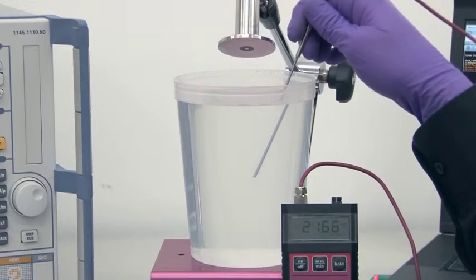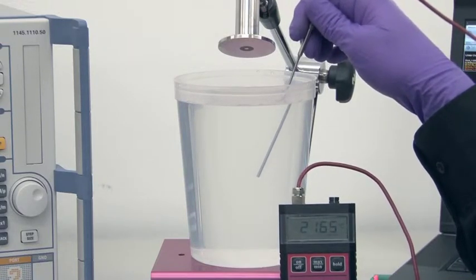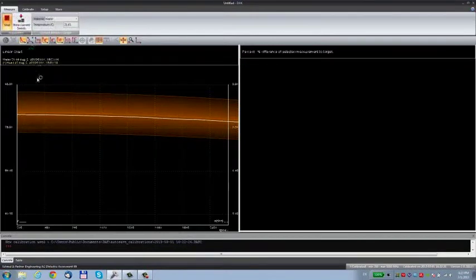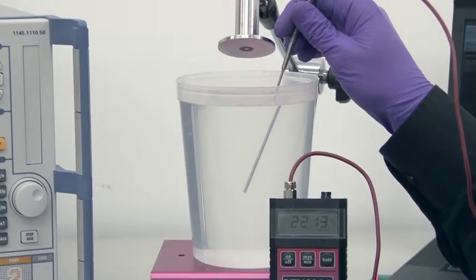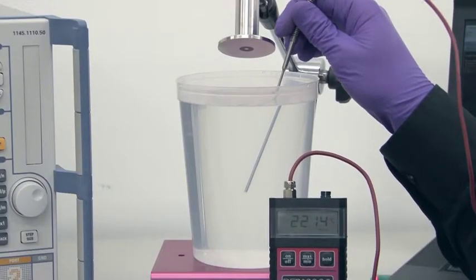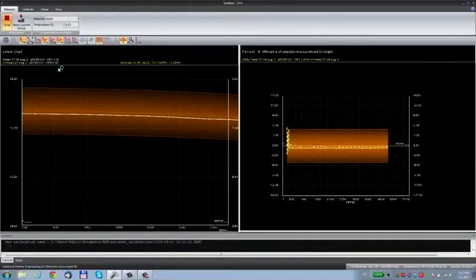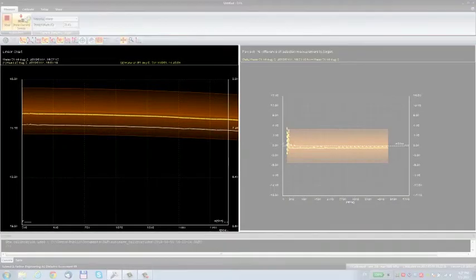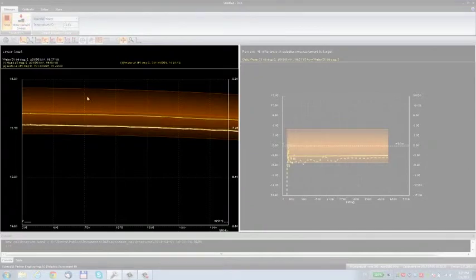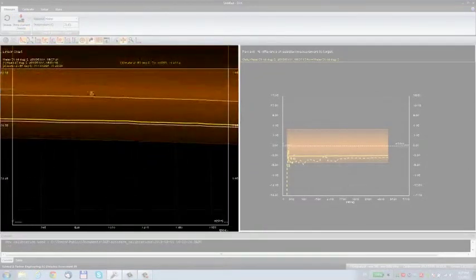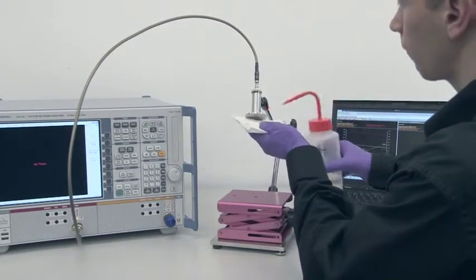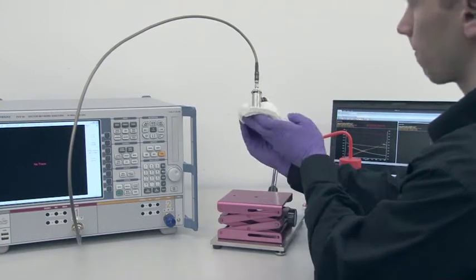Let me show you what is the effect of the temperature drift. I measure water at 21.65 centigrade and store it in the software. When the water is 0.5 centigrade warmer, the measured curve shows different values. By remeasuring periodically the liquid temperature, you can improve the measurement precision. When you finish the measurements, clean the probe.